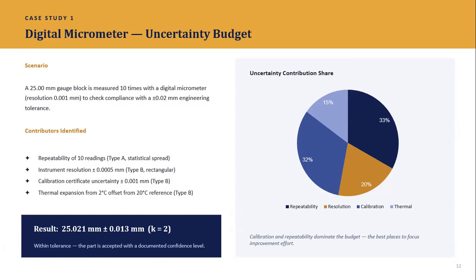The resulting measurement is reported as 25.021 millimeter plus or minus 0.013 millimeter with a coverage factor of 2. According to the case study, the part is within the tolerance and can therefore be accepted with a documented confidence level. An important lesson here is that calibration and repeatability are the significant contributors to the uncertainty budget, and therefore they provide useful targets for improvement.